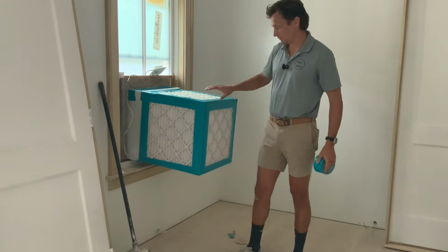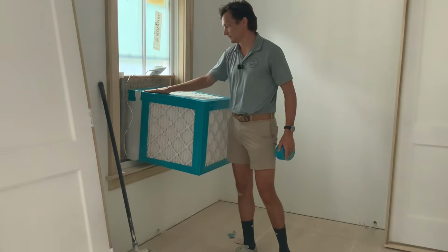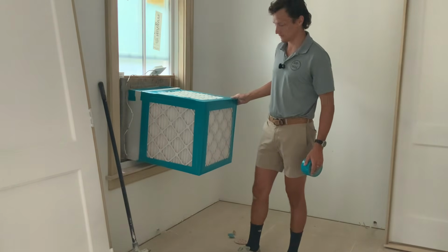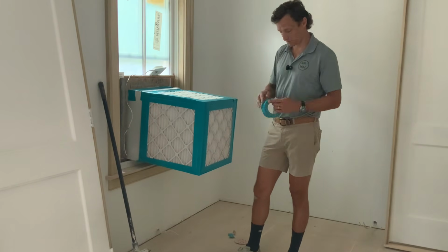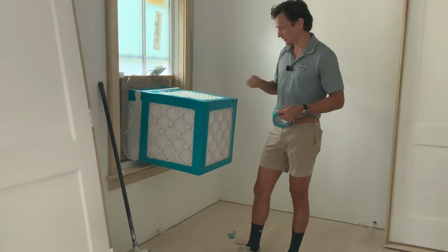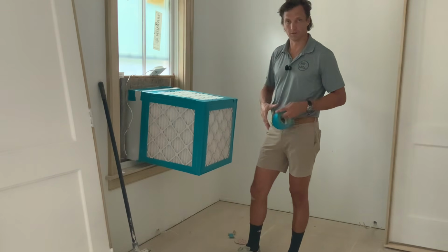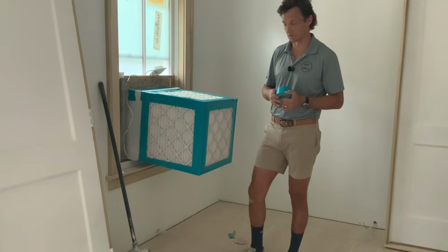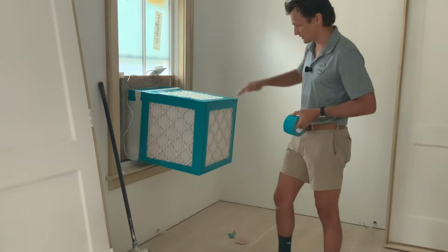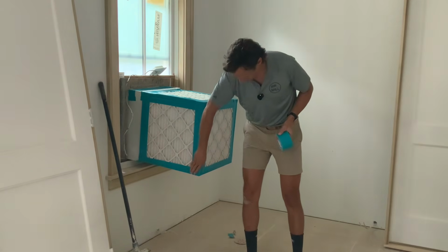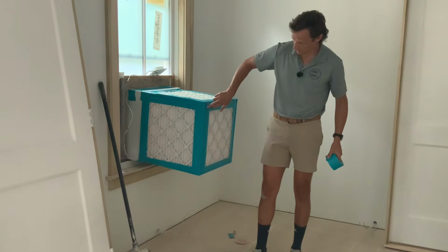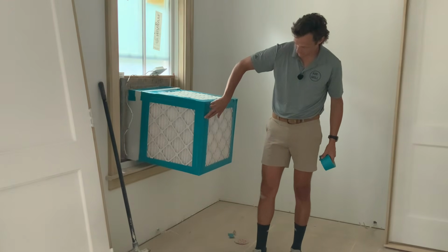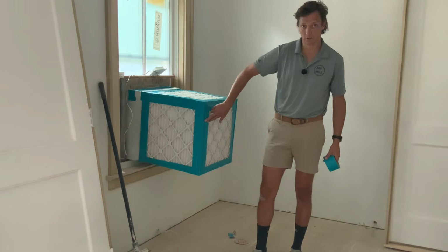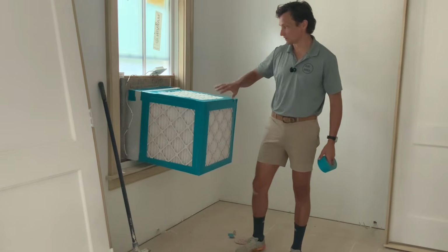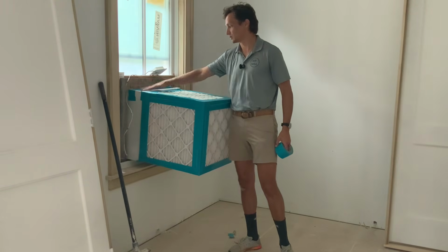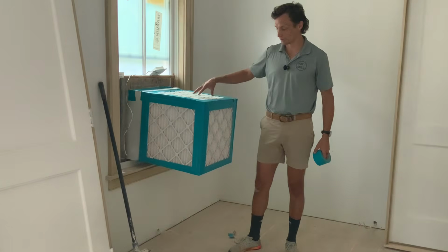So the duct tape is not here to hold the filters in place. If that was the case, we could just put a few little tabs of duct tape all the way around and hold the filters in place. We spend thousands of dollars on duct tape every year doing the filters like this because we need to create an airtight seal between the box and the filter to protect the machine, to make sure that all the air that's getting sucked back into our machine is getting forced through the filter box.